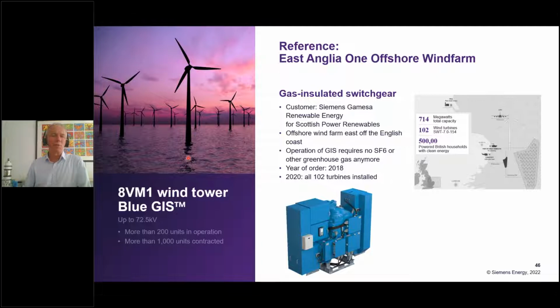originally the medium voltage connection from 33 kV was increased to 66 kV to lower the losses. And the next step also in Europe, offshore wind, will be to double that to 132 kV. So the projects realized in 5 years will have so much wind power generated that the energy is transmitted at the voltage level of 132 kV.